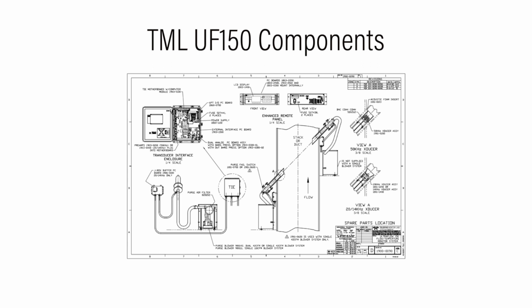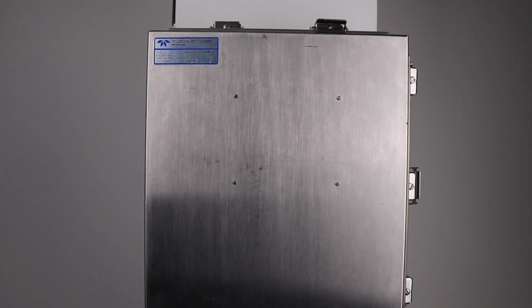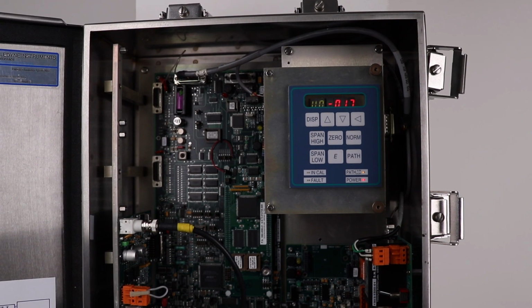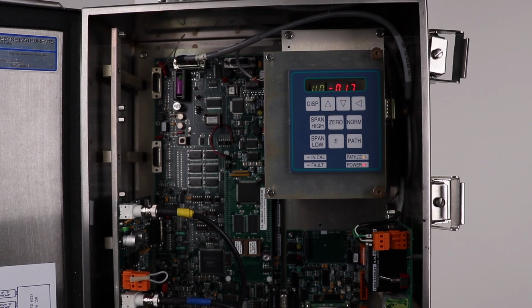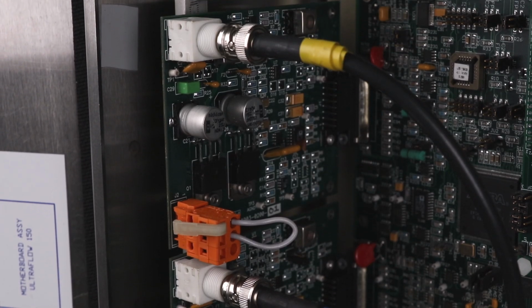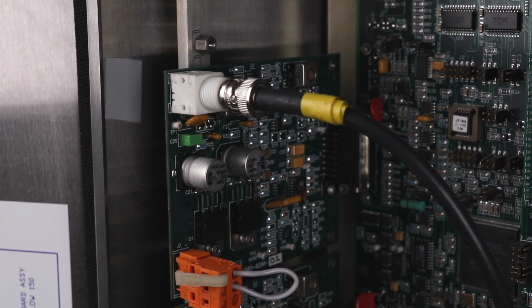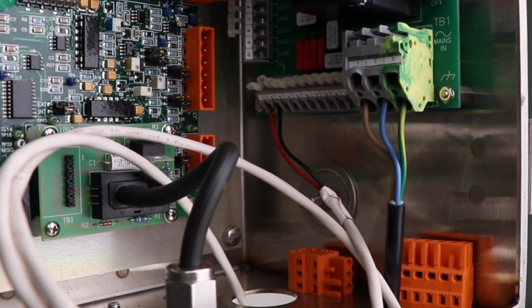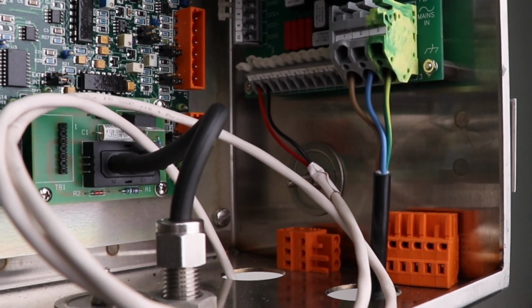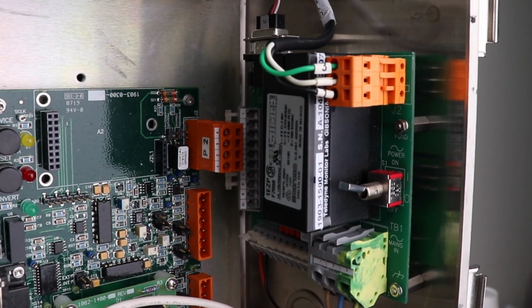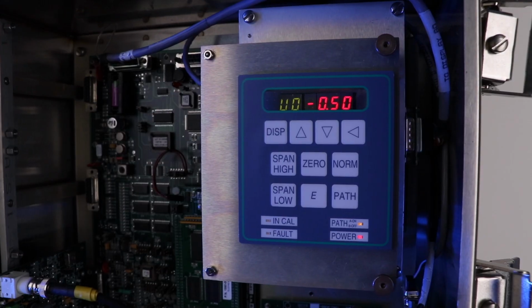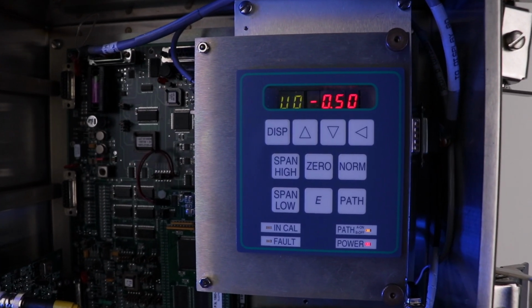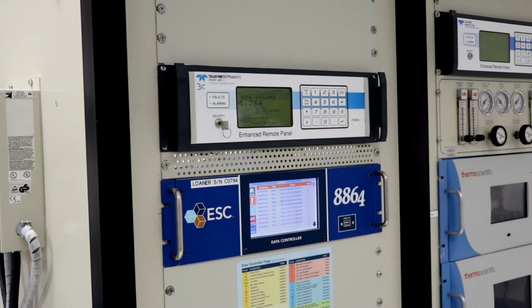Now let's talk about each component of the UF-150. We'll start with the Transducer Interface enclosure assembly, or tie box. The tie box contains the electronics that control the transmit and receive signals from the transducers. This includes the preamp board, analog board with barometric pressure sensor, external interface board, power supply, and the local user interface. The data is then transmitted to the enhanced remote panel, or ERP.